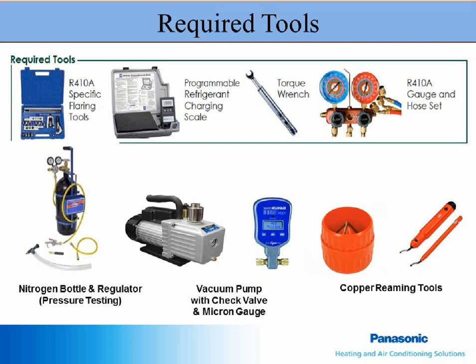If brazing is needed, then purging with nitrogen while brazing is required to prevent oxidation from building up inside of the copper and contaminating the system. Nitrogen is also needed for leak checking. Humidity in the air contains moisture, so a vacuum pump is needed to remove it and any other contaminants that are in the lines. To allow this moisture to boil, a vacuum of 500 microns must be attained. Microns can only be read with an electronic micron gauge.